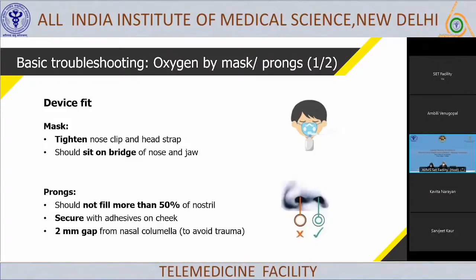Then we also need to keep in mind the leaks and obstructions. Many of us may take this for granted and think that this is not our job. But the issue is that if we figure out there's a leak, we need to make sure that the leak is taken care of. Otherwise, we are going to waste a lot of oxygen. You need to check the tubings and connections. There would be times when children or older children are breathing by mouth with nasal prongs. And in that scenario, again, the delivery of oxygen is going to be compromised, and therefore, in that setting, you modify it. Similarly, you need to check regularly for nasal secretions and obstruction, and the patency of the nasal prongs.